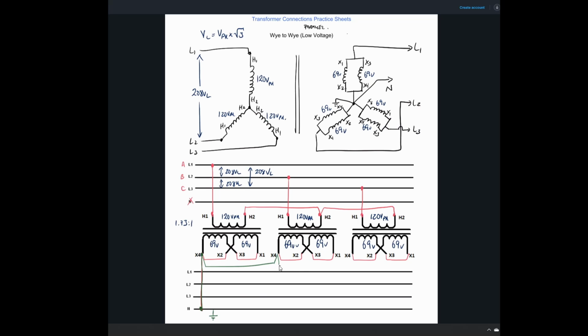Okay, hard to keep these diagrams nice and neat. Now we're all at the same potential with our 2s and 4s, and they're being brought down to this neutral connection here. Then, if we label these transformers 1, 2, and 3, and these would be the secondaries 1, 2, and 3, then the first transformer, X1 and X3, is going to feed line 1 out. Then the second transformer, X1, is going to feed line 2 out. And then the third transformer, X1, is going to feed line 3.